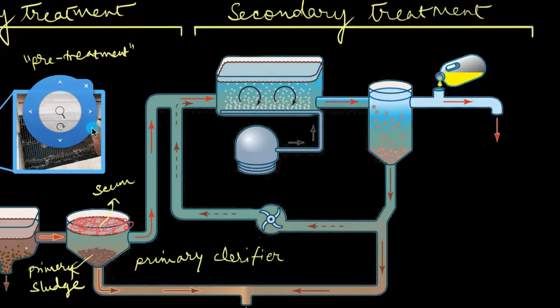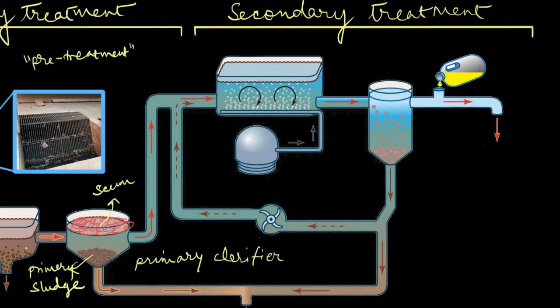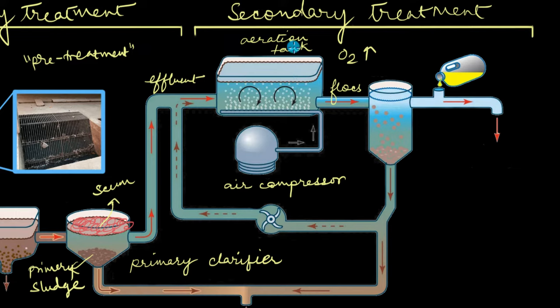Secondary treatment or biological treatment hinges on the activity of microbes. The slightly treated water from earlier, which is also called the effluent, now goes into these aeration tanks. The purpose of this aeration tank is to blow air bubbles into the water, which is done with the help of an air compressor. It's constantly blowing air bubbles into the water and that increases the levels of oxygen. The already present aerobic bacteria and fungi in the water thrive in all of this oxygen and digest the organic matter present.